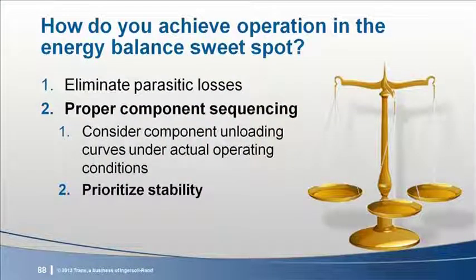Another topic that does not normally come up in the discussion of component sequencing is the importance of stability to system efficiency and reliability. One of the reasons I mention it here is that there are optimization strategies that depend on a method of regularly turning things on and off to see if it results in more efficient system operation. This methodology would make you believe that optimization is unpredictable. However, it is predictable, and such trial and error methods ignore the fact that even with VFDs acting as motor soft starters, every operating cycle introduces system transients that result in additional wear and tear on multiple system components.